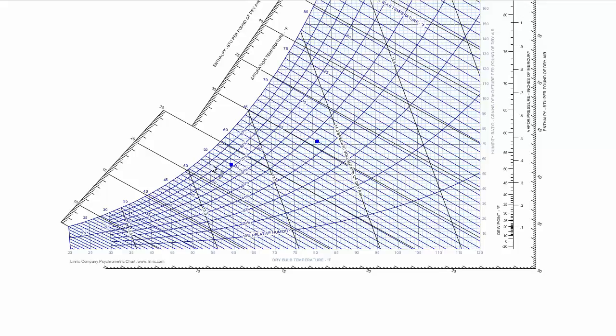Any point horizontally from 51 on this curved section is said to have 51 degree dew point temperature. So when they say on the news the dew point outside is 51, the actual conditions could be anywhere along this horizontal line. That's just saying that if that air is cooled to 51, that's when condensation will start to form and water vapor will come out of the air.